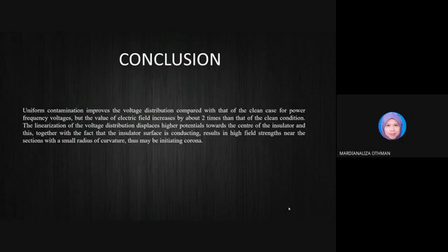The linearization of the voltage distribution displaces higher potential toward the center of the insulator, and this, together with the fact that the insulator surface is conducting, results in high field strength near the section with a small radius of curvature, thus possibly initiating corona.